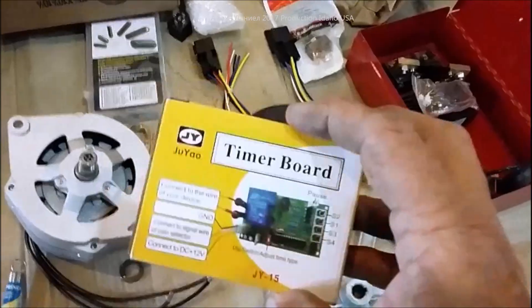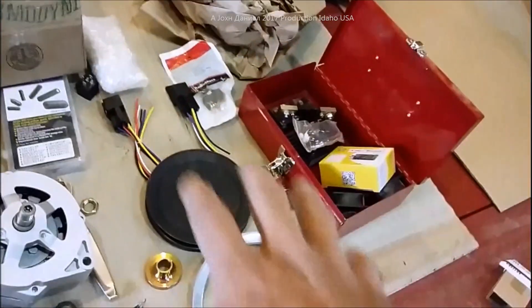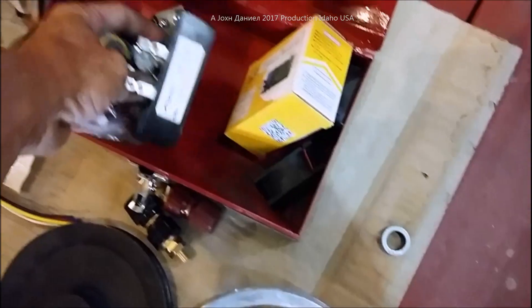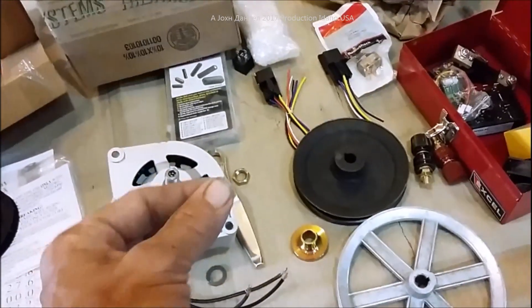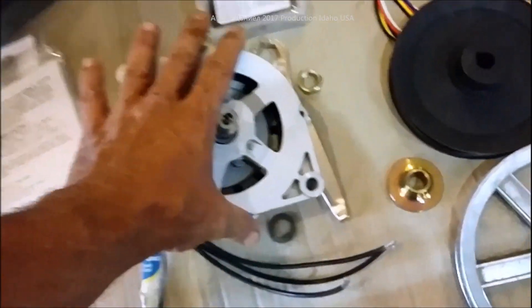The timer board will let me set a run duration — if I see I'm at 11.5 volts, I know from experience this engine can bring the system back up in about 45 minutes. What we're building is a gasoline-powered DC 100-amp battery charging system. This is not like engine-start mode on big battery chargers — those just jack the voltage super high to force a current spike. We want pure, clean power for proper battery charging.